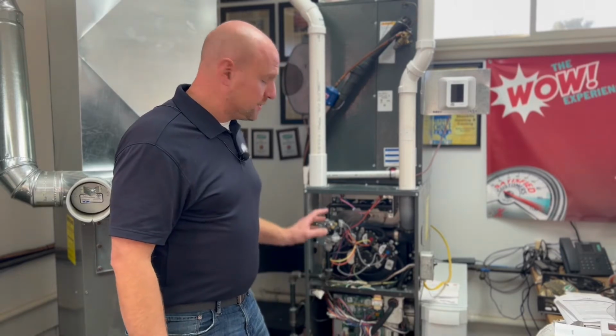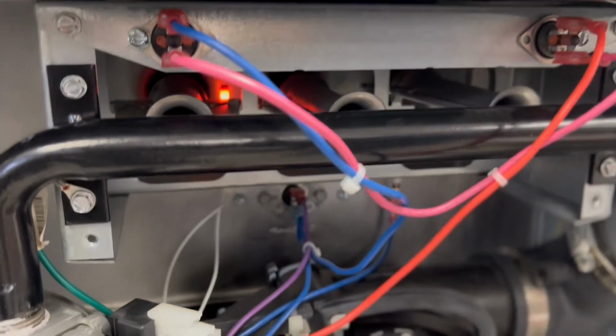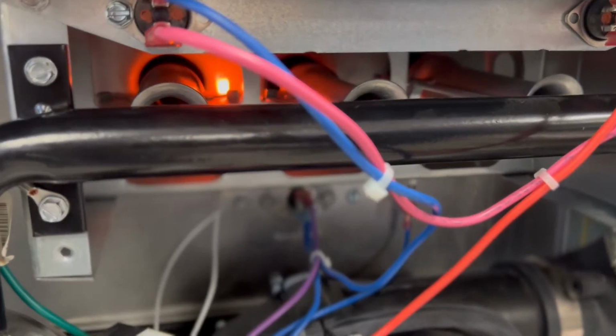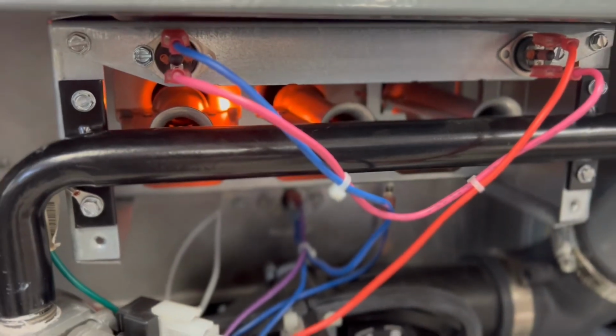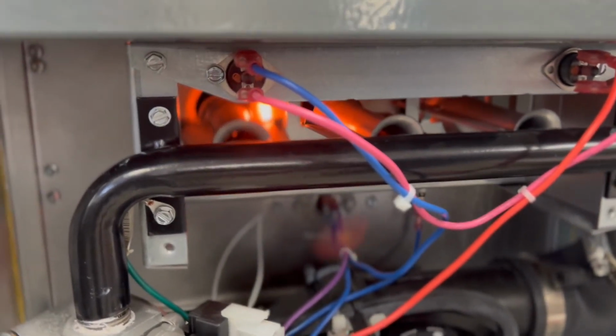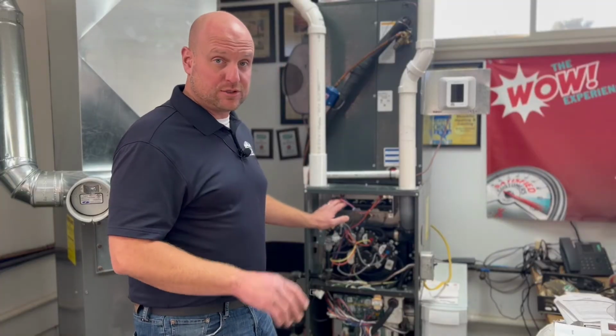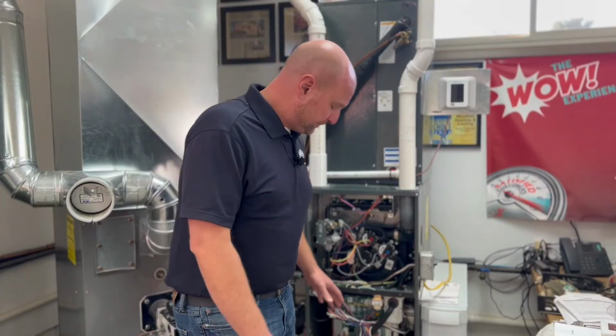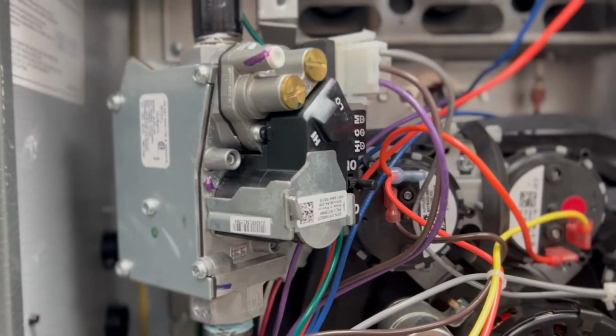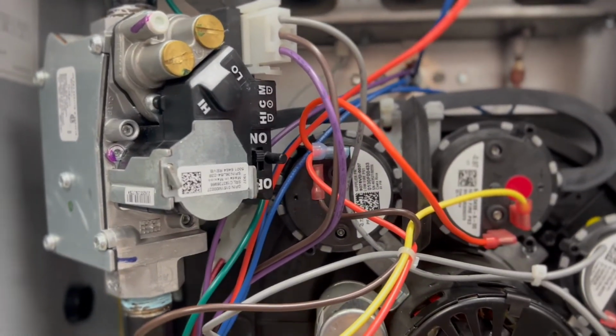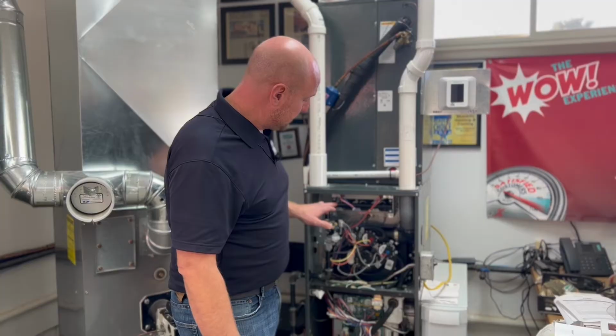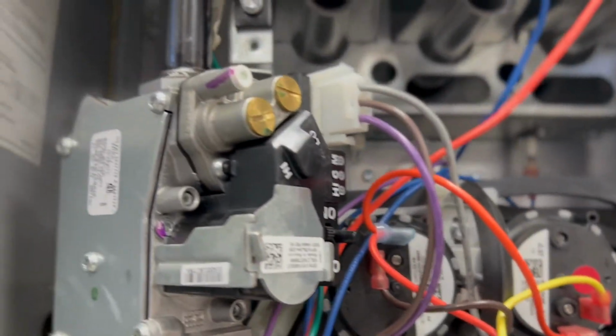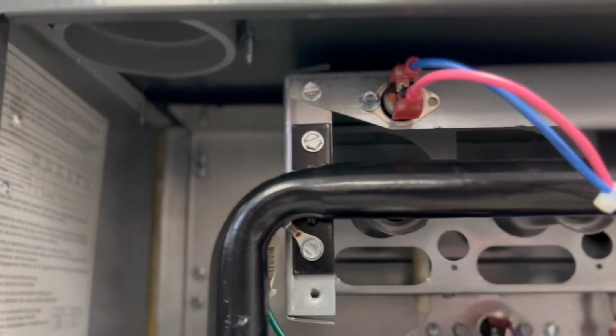After this, the circuit board is going to send power up to our hot surface igniter, which is going to turn on and light up and get hot for about 15 to 20 seconds. Once it is up to full temperature, the circuit board is going to send 24 volts to the gas valve. This will cause the gas valve to open. It will go ahead and let natural gas come out of the burner bar into the burners and light.